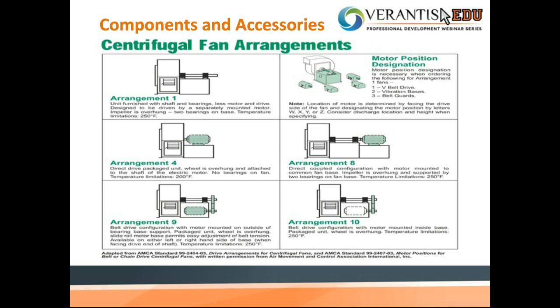The next one you'll see is arrangement 4, and basically that is a direct drive fan. That is where the motor of the fan is directly coupled to the shaft of the impeller. And arrangement 8 is an inline arrangement where the fan base is extended, and we'll use a special coupling for that type of arrangement that hooks up the motor shaft to the shaft of the fan. What you notice as the difference between arrangement 4 and arrangement 8 is that arrangement 4 has no bearings in the arrangement, whereas arrangement 8 has an inboard and an outboard.